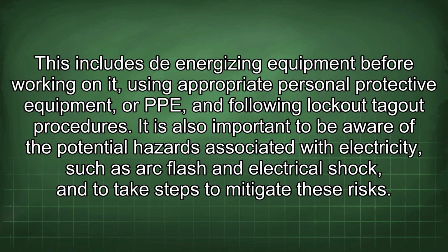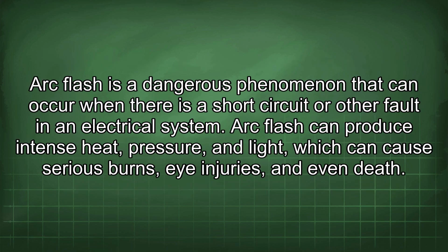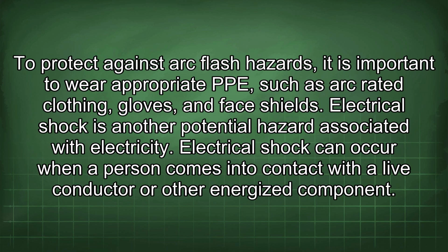This includes de-energizing equipment before working on it, using appropriate personal protective equipment, or PPE, and following lockout-tagout procedures. It is also important to be aware of the potential hazards associated with electricity, such as arc flash and electrical shock, and to take steps to mitigate these risks. Arc flash is a dangerous phenomenon that can occur when there is a short circuit or other fault in an electrical system. Arc flash can produce intense heat, pressure, and light, which can cause serious burns, eye injuries, and even death.